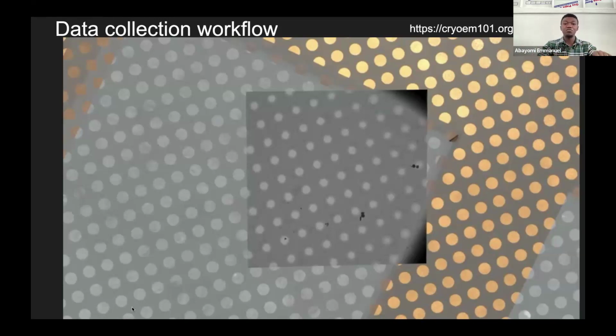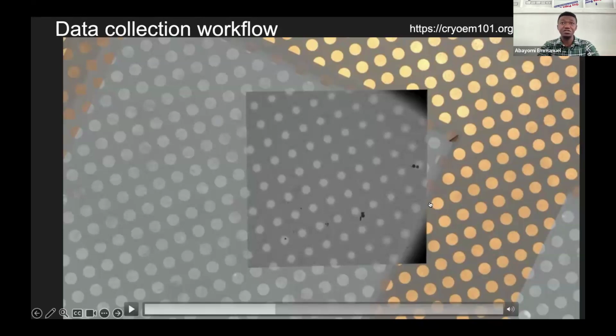Then you try to look for where there's no ice contamination. All right, you know, at minus 80 degrees, you expect that you can see some ice crystals. But here, you don't want any ice crystal on your sample. You just want to be able to image your sample. What you were seeing the other time, all these black dots, they are ice contamination. So you don't want that.